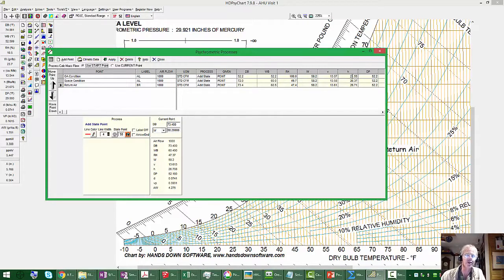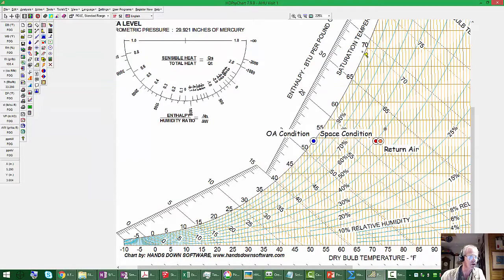That's sort of misleading because we think of relative humidity, but when you're working with HVAC, you really need to think of specific humidity. And what I mean by that is, if I could magically take a cubic foot of that foggy outdoor air and bring it into the building and let it warm up without letting mass transfer to or from that cubic foot. In other words, energy could get in and warm it up, but mass couldn't. Basically, you would move horizontally across the psych chart, right? Because a psychrometric process that only had sensible energy is a horizontal line on the psych chart, be it a constant specific humidity, a constant dew point.